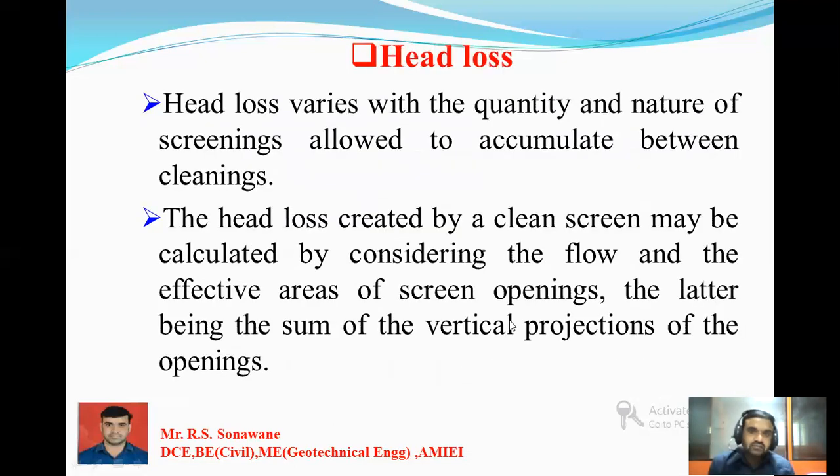Now, the second term that is very important is head loss. Head loss varies with the quantity and the nature of the screenings allowed to accumulate between cleanings. In particular, with accumulation between cleanings, the head loss varies across the screen. The head loss created by a clean screen can be calculated by considering the flow and the effective area of the screen opening, the latter being the sum of the vertical projection of the openings.